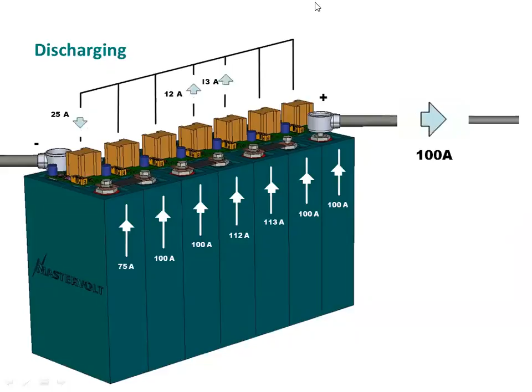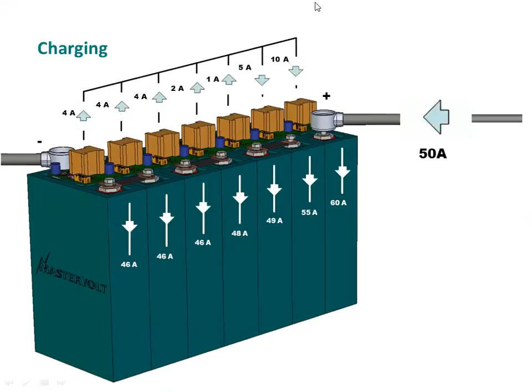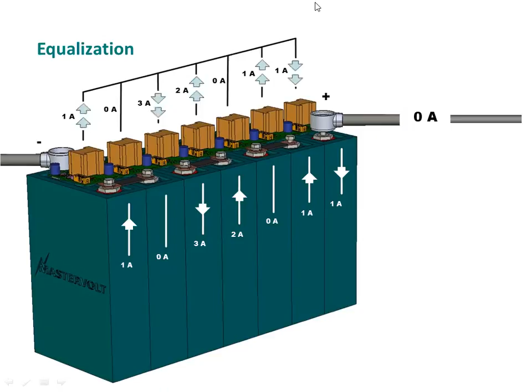So you're putting 50 amps in, but one battery cell takes 60 amps, while another cell only takes 46 amps. This whole balancing process works while you're charging and discharging, but even when you're done and there's no current going in or out, the system stays active until all the cells are equally recharged. This is key to the success of a lithium battery bank, because if people don't use a BMS, you're not getting the full capacity out of your battery bank.